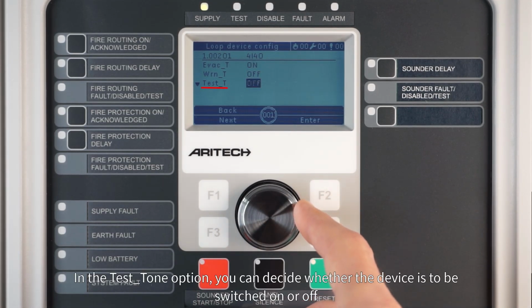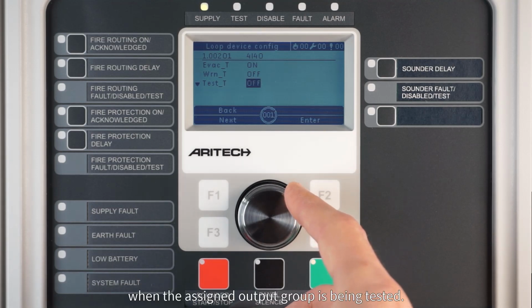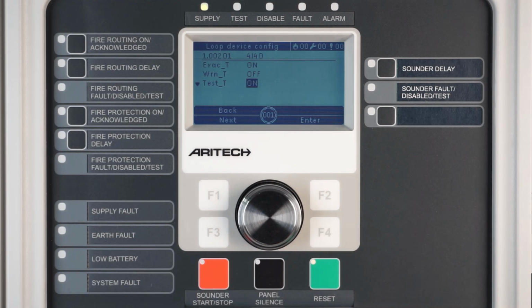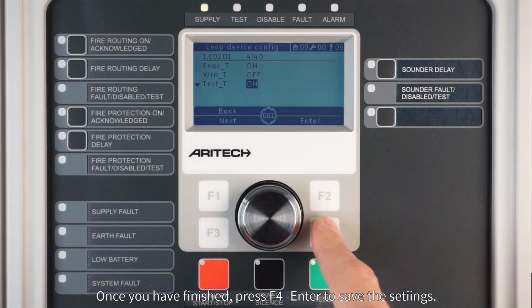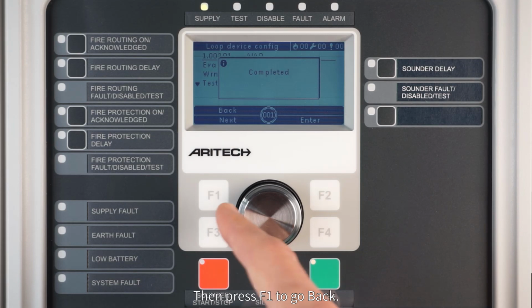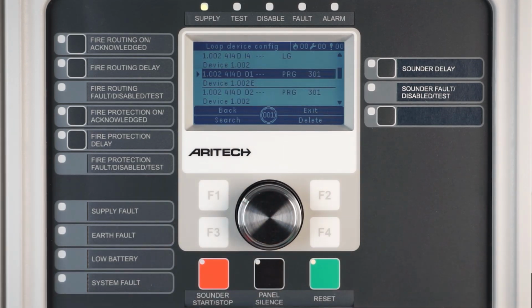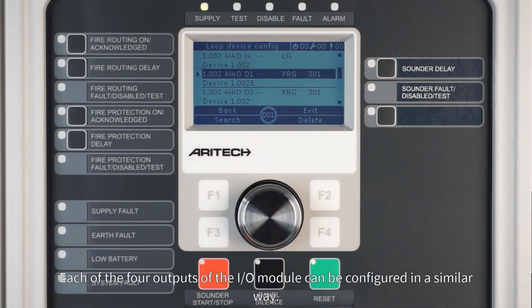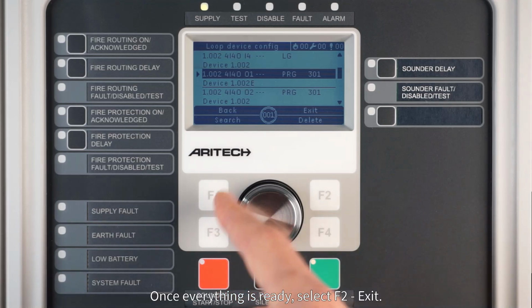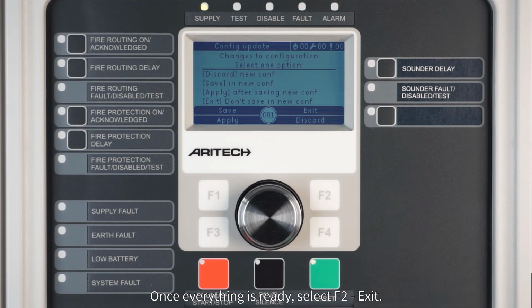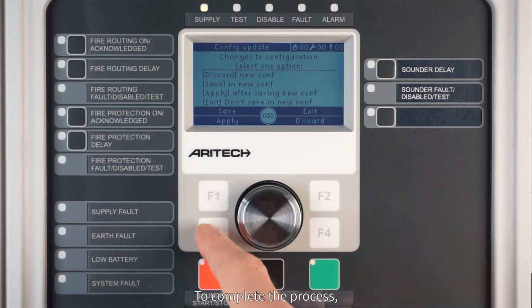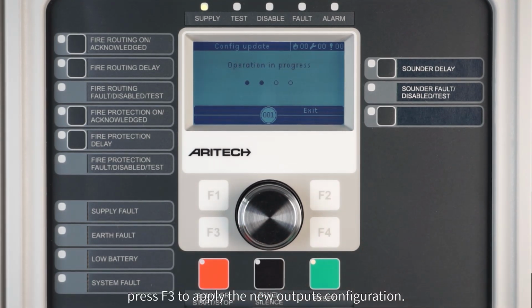In the test tone option, you can decide whether the device is to be switched on or off when the assigned output group is being tested. Once you have finished, press F4 enter to save the settings. Then press F1 to go back. Each of the 4 outputs of the I/O module can be configured in a similar way. Once everything is ready, select F2, exit. To complete the process, press F3 to apply the new output's configuration. The changes will take effect after the panel reset.